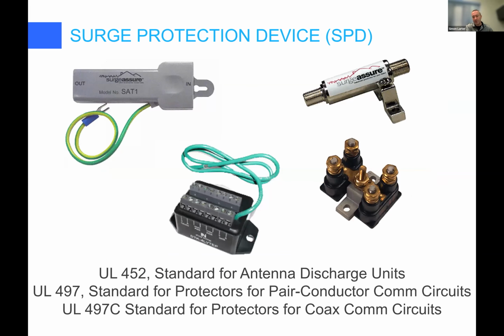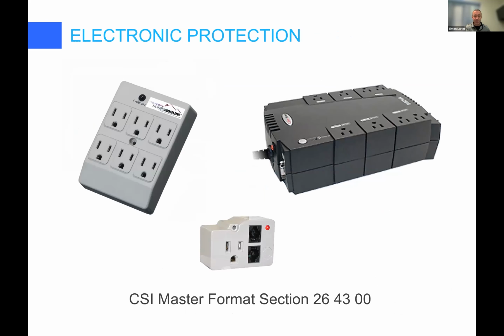And of course, you've got all the antenna, coax, telephone wire, twisted pair, all of that stuff. UL has standards on those too. Again, you will rarely be called upon to inspect that kind of thing in terms of looking at lightning protection systems, but you have to be aware of it because it is an essential component of lightning protection. And of course, that's just a good idea. You can have multiple tiers of surge protection, and every data center does. We do a lot of protection for data centers, so they have both type 1, type 2, and then point of use. Lots of people try and use that too as an electrical safety thing.